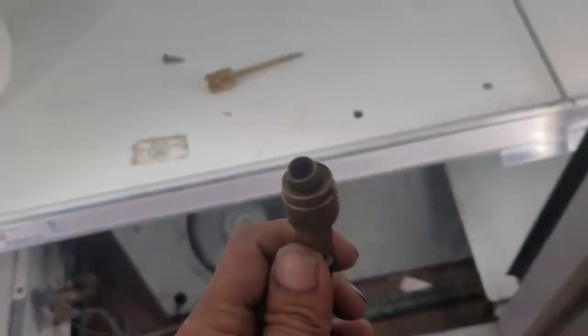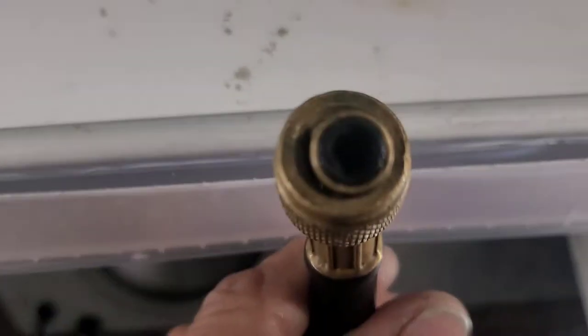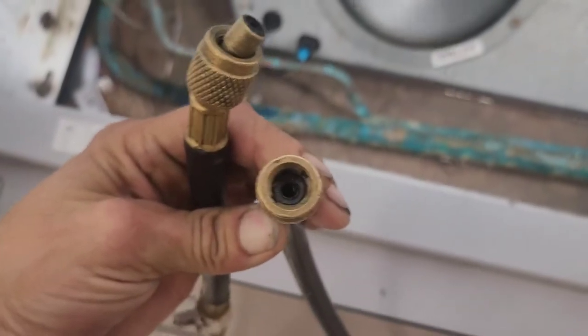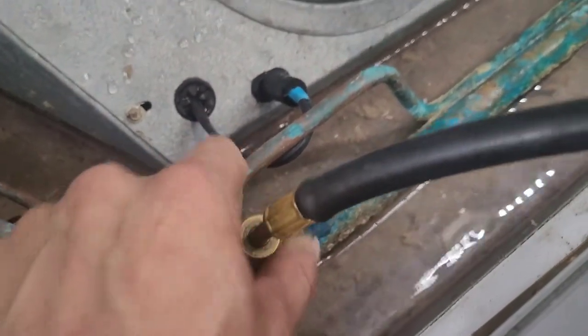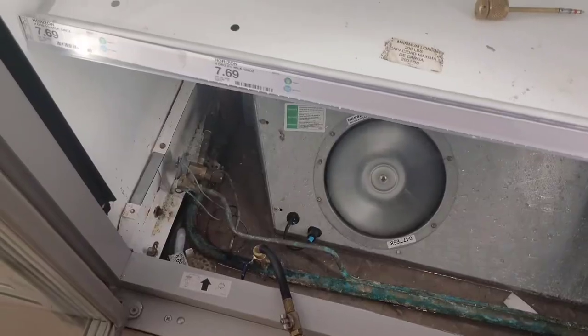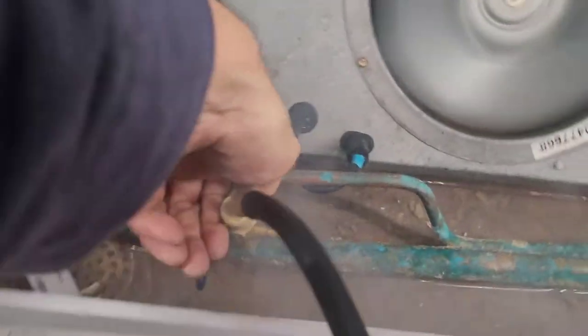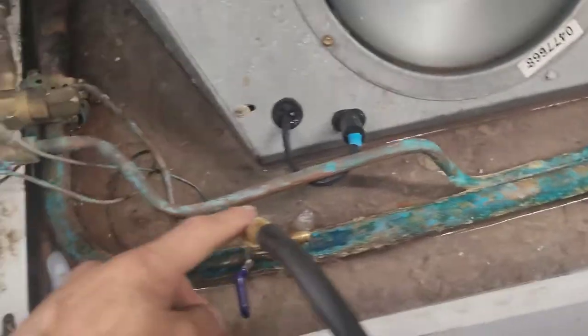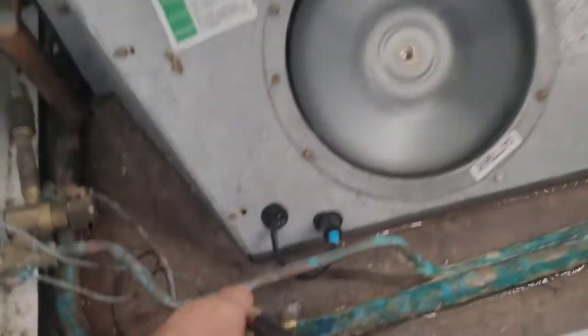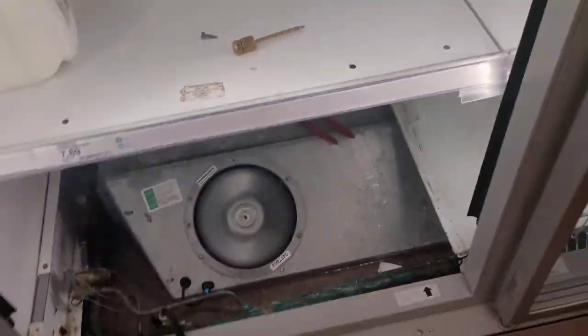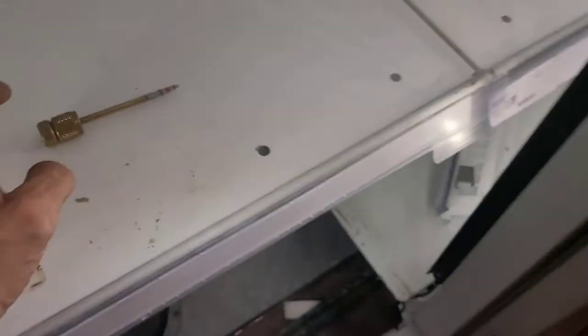And once you have the valve stem out, you want to make sure that you don't have any of those little valve stem depressors in your gauge hose. You want to have your clear hose. Connect the hose to the bottle, then connect the hose to the tool with the valve closed. Leave this cracked just a little bit so you can purge it. Then, of course, just purge it. You know how to do that. And then, with no restrictions anywhere, it's going to go in very quickly. Much quicker than it would with the restrictive things like a valve stem in there, at least.